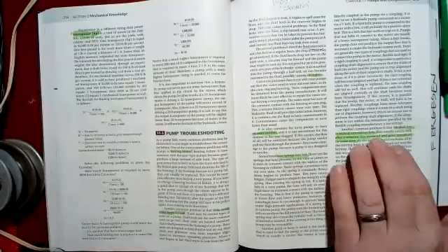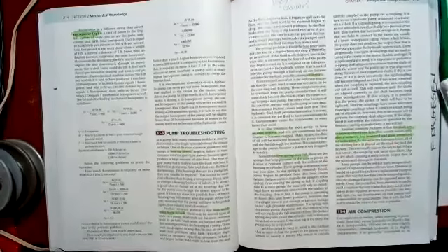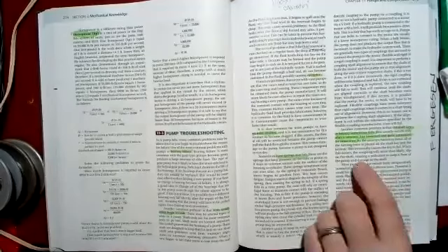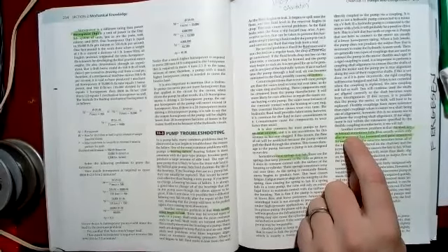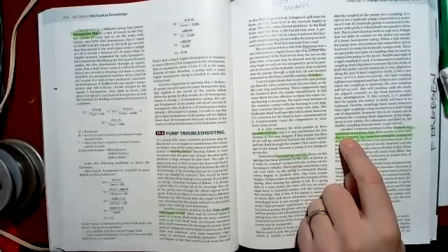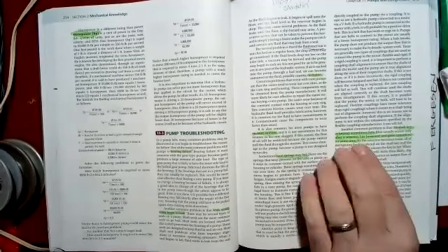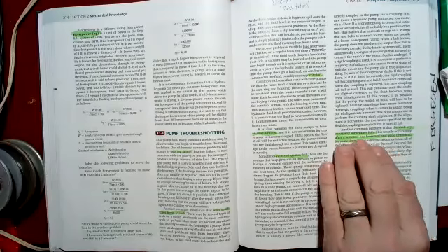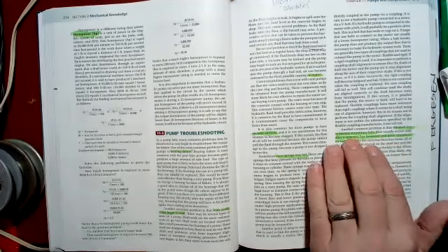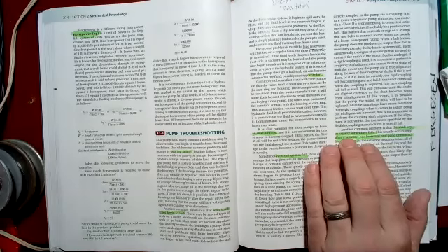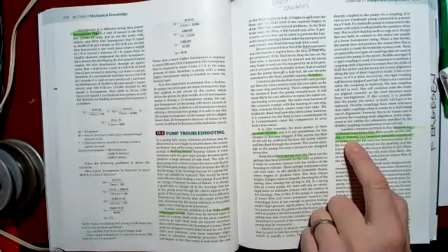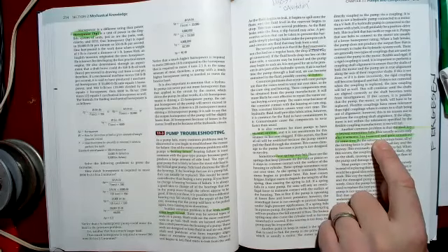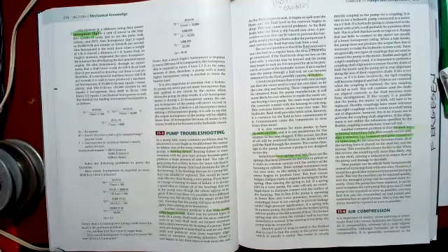Another thing down here I highlighted is that sometimes you get major problems on your shaft and you get keyways that shear off. Those are just soft steel keys. As we learned in the lab, sometimes they just shear off if there's too much force over them. Sometimes the steel begins to develop some flaws just by time and force. And the most common thing is set screws become loose. So you should always check to make sure your set screws are tightened and stay tight.